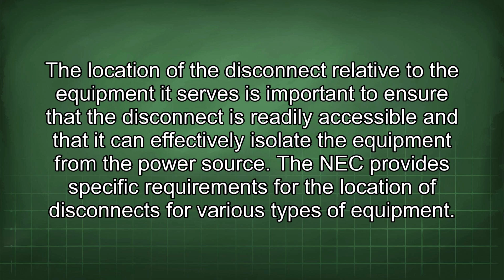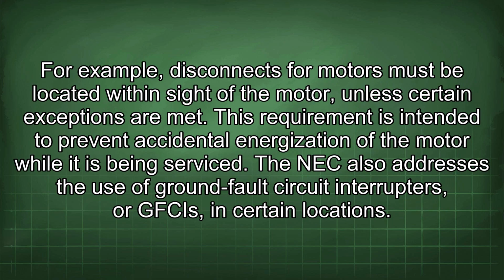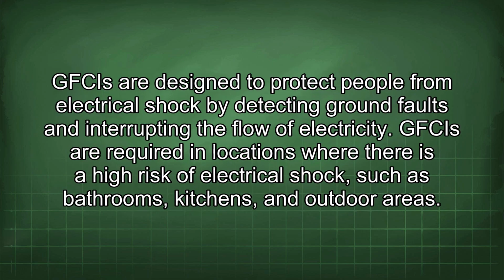The NEC provides specific requirements for the location of disconnects for various types of equipment. For example, disconnects for motors must be located within sight of the motor unless certain exceptions are met. This requirement is intended to prevent accidental energization of the motor while it is being serviced. The NEC also addresses the use of ground fault circuit interrupters, or GFCIs, in certain locations. GFCIs are designed to protect people from electrical shock by detecting ground faults and interrupting the flow of electricity.